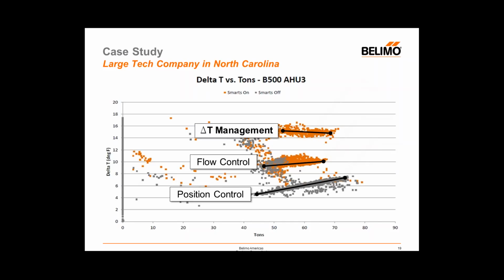A couple of weeks go by and they engage Delta T Manager. Now, with the Delta T Manager, there's a couple of ways to get your delta T management set point. In this case, they just sort of tinkered with it. They probably set it at 12 and saw they could meet demand, and then they tried 13, 14, 15, 16, 17. At some point, they found they couldn't cool the space. So they settled right around 15 degrees F. And so now, with delta T management in place, that's still between sort of 50 and 70 tons range, they're cooling the same space with the same equipment with significantly less water because they have a higher delta T.